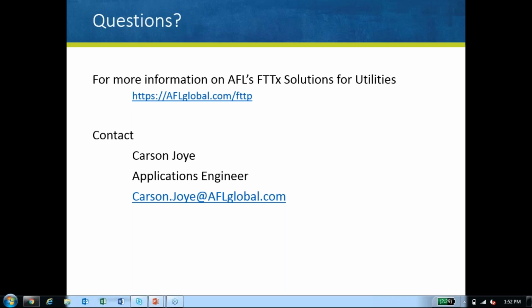Matt Sedgwick asked, where does the supply space end, at the neutral or at the fiber? That's a great question, and often misunderstood. If you're placing fiber in the supply zone, you are resetting your supply zone. So if your ADSS is below the neutral, then the supply zone would end at your ADSS.